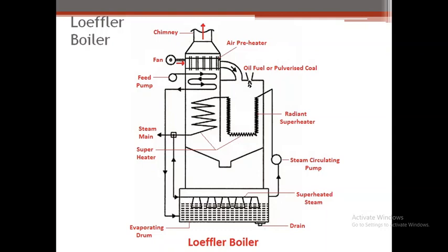Now let us see the disadvantages of this Loeffler boiler. The evaporating drum is costly and bulky in size. The further disadvantage is that bubble formation occurs, which creates a problem for the heat transfer rate. So these are the disadvantages of this Loeffler boiler.